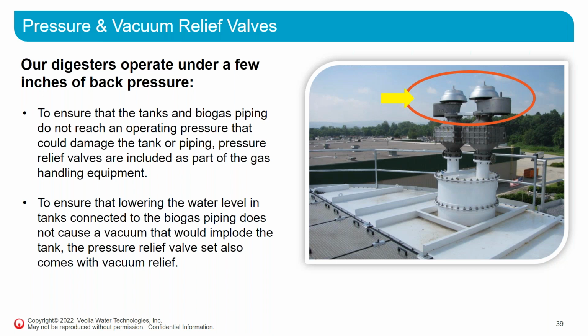Also, if you have pressure events, it's important to inspect them. You don't want to have leaks in your system if things degrade. And to clarify, the overpressure may be obvious, but the vacuum relief is included because if you have a sudden drop in level in either the tank or the connected piping, you wouldn't want to accidentally create a vacuum in the system.